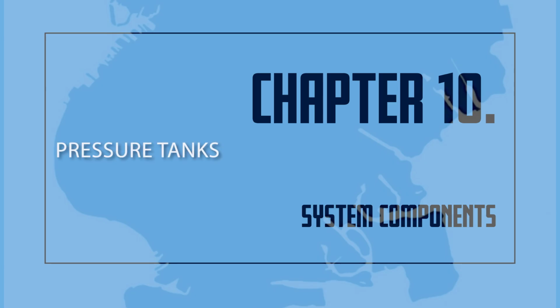Pressure tanks. Pressure tanks are enclosed water tanks of limited size. Air pressure in the tank permits forceful discharge of water in the tank into the sprinkler system. A pressure tank may be used as a primary or secondary water supply for a sprinkler system. A pressure tank is usually housed in an enclosed structure. The temperature in the enclosure is kept at 40 degrees Fahrenheit or above. The heated structure may be located anywhere inside or even outside of the building.